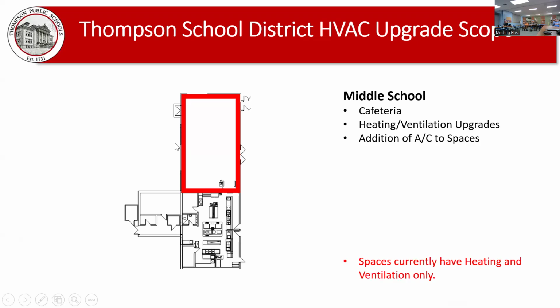So we have a ground-mounted unit programmed right outside, just to frame this area. There's a back entry that comes in this way, and a ConVault tank up here for fuel oil. Not a high-profile aesthetic area, so we do have a ground-mounted unit here. Looking structurally at this, there are bar joists that run across wall to wall with no support whatsoever, so it would be a significant dunnage effort if we tried to get it on that roof. From a structural standpoint, we went with the ground mount unit outside here. We'll have supply and return duct going up onto the roof, and punch down supply and return. That would be 100% outside air, ventilation, and addition of AC.